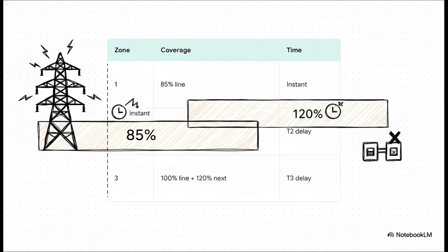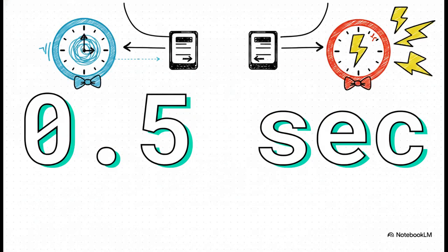Zone 2 then steps in to cover that 15% blind spot by extending out to 120% of the line, but, and this is absolutely key, it intentionally waits before taking action. That waiting period is typically around 0.5 seconds. Now, I know half a second sounds like a literal blink of an eye to you and me, but in the world of electrical engineering, half a second is an absolute eternity.